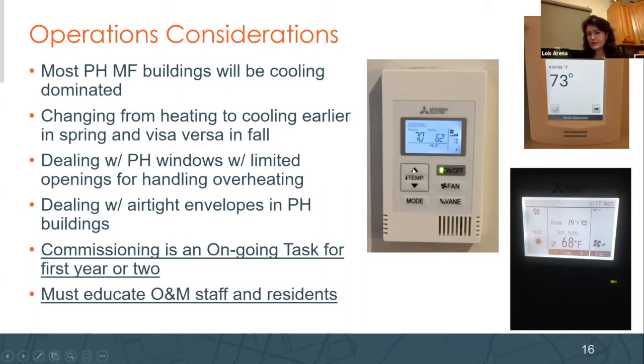These three thermostats are from 3 different VRF projects in heat pump mode, and they are showing you that the set point on the thermostat is way lower than what this one's off, and this, they're way lower. And this one here was 30 degrees outside, this one was 40 degrees outside, and I think this one was about 50 degrees outside. That was just recently. So these people wanted a cool apartment, but they can't get a cool apartment even with their windows open. So really keep that in mind when you're doing this.